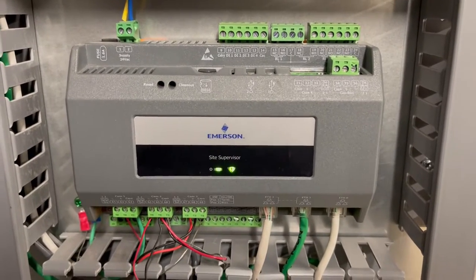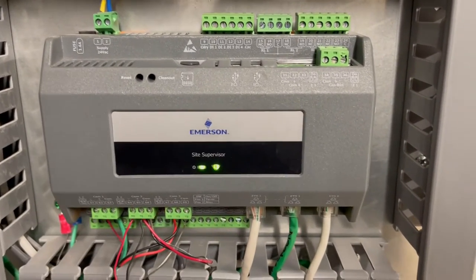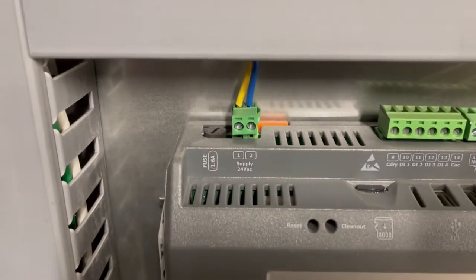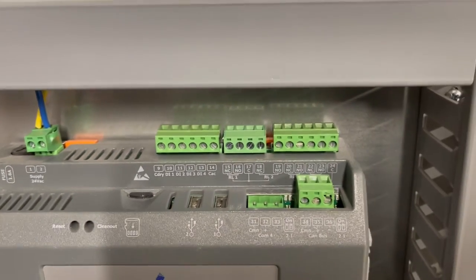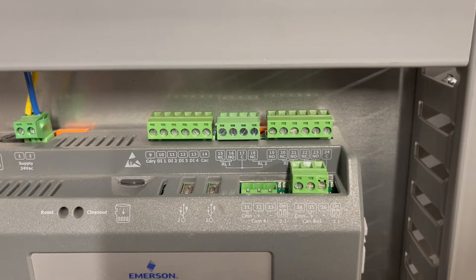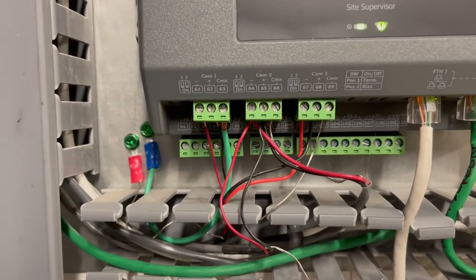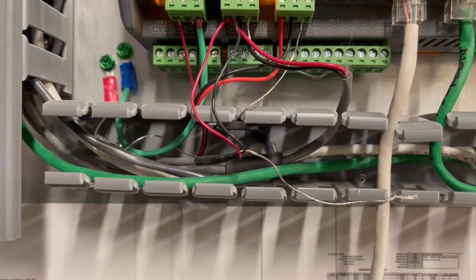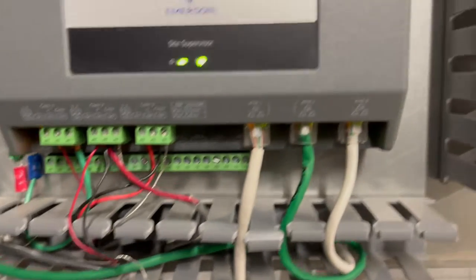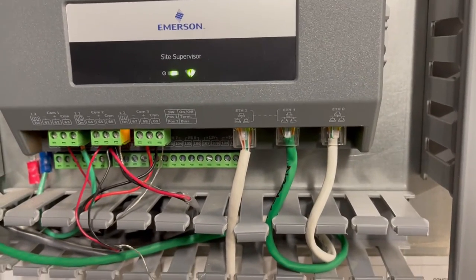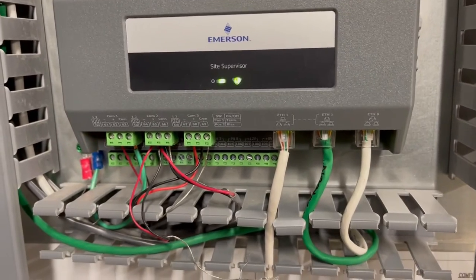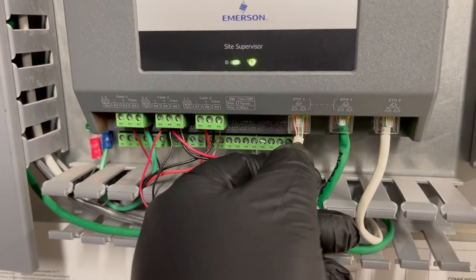Running back the video, this time instead of an E2, E3, the Site Supervisor controller. This is the one that's going to be replacing the E2s. Got the 24 volts to the left. You got already built-in boards in there, DIs, ROs, the COM, and right underneath that is for the AIs. As you can see, it already has a board built in the controller. And that's where the Ethernet Cat 5 wires go into, where you can put your screens, because this controller does not need a screen to operate, but you can apply for the technicians.